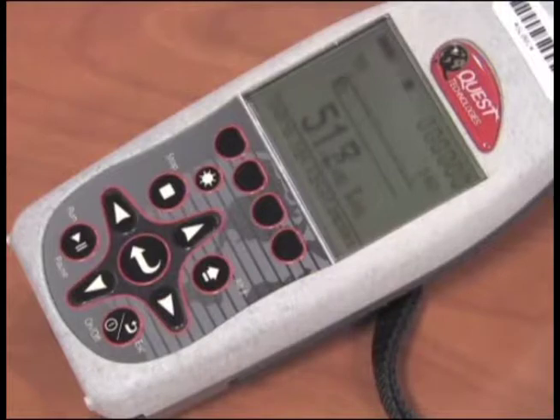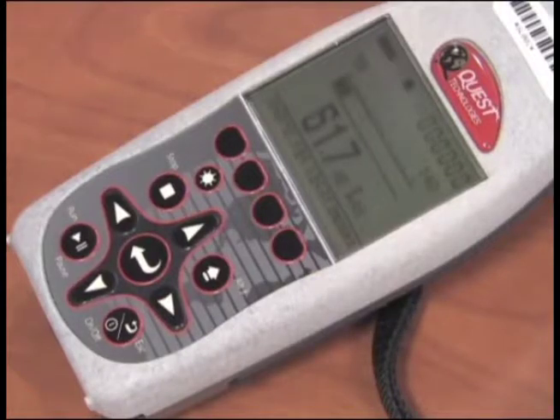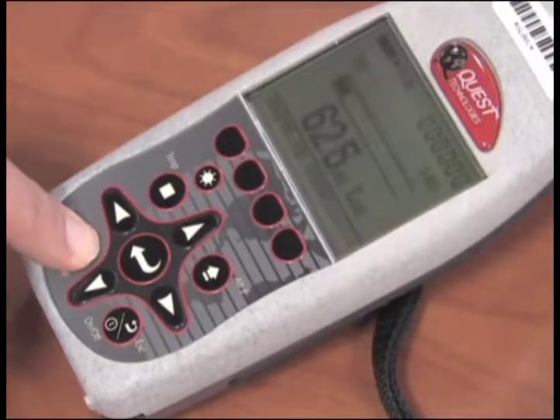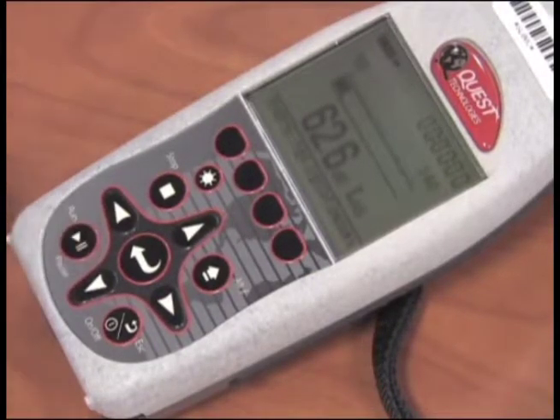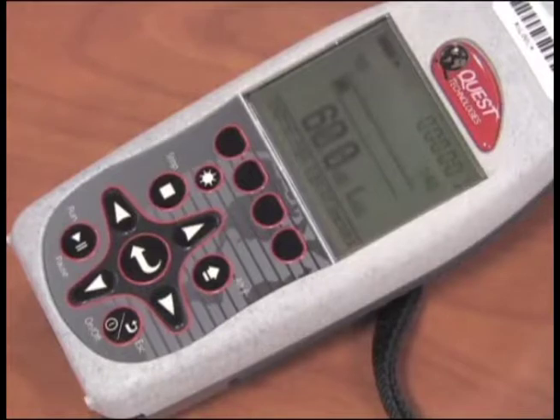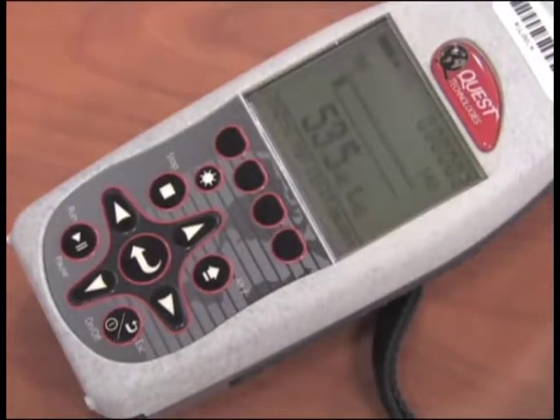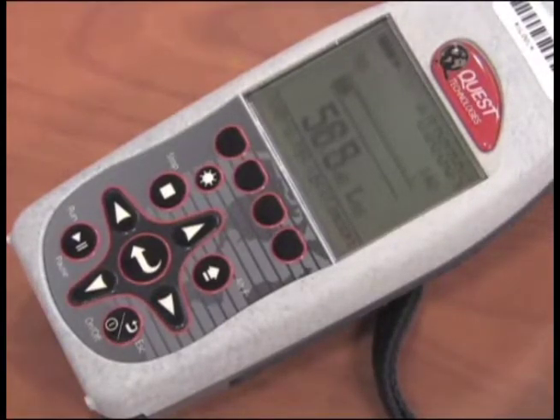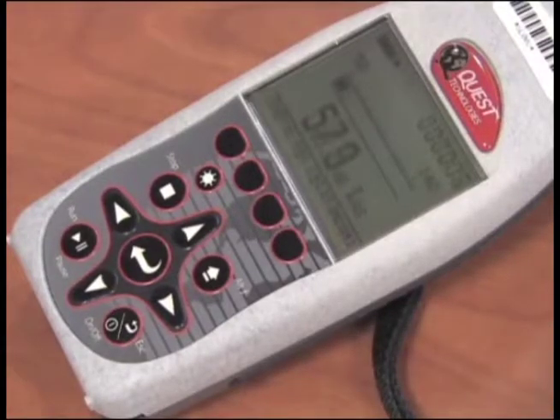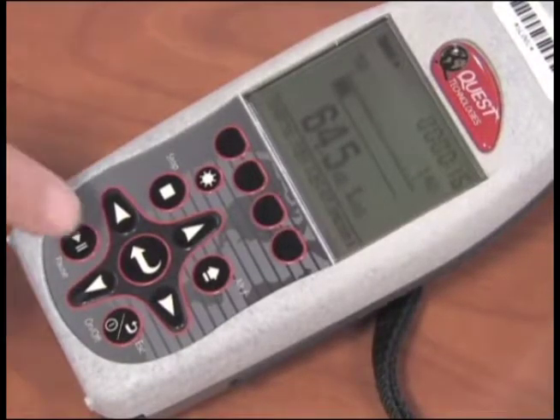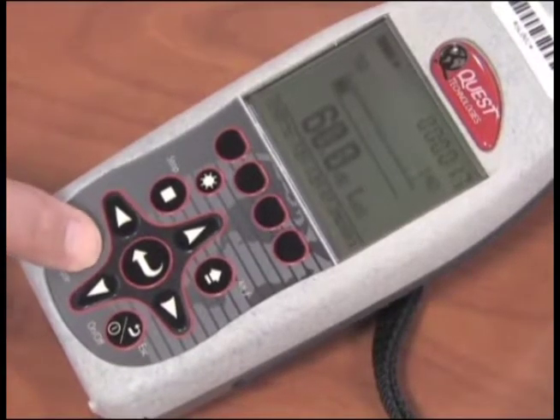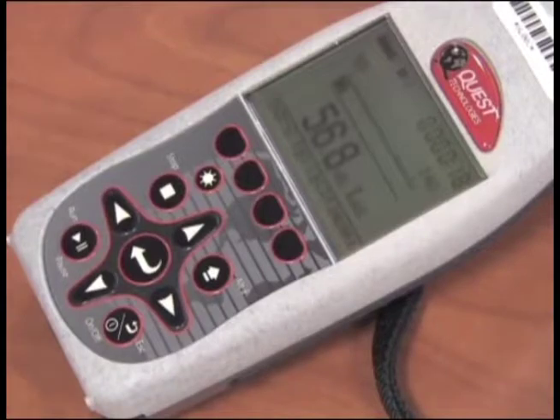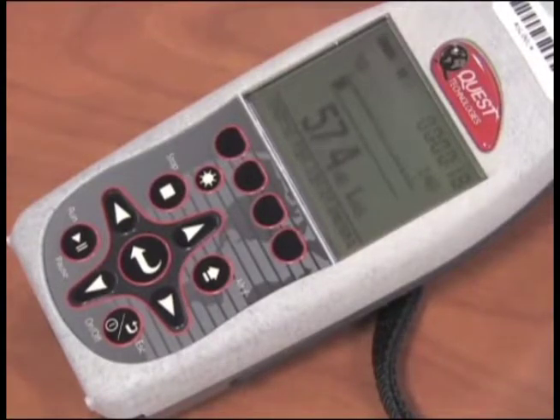The unit is not data logging at this time. To data log, push the Run button. An arrow will appear in the top left-hand corner of the screen and a timer begins. When your survey is complete, pause the unit by pushing the Run-Pause button. The arrow changes to a double bar. This creates a study within a session.